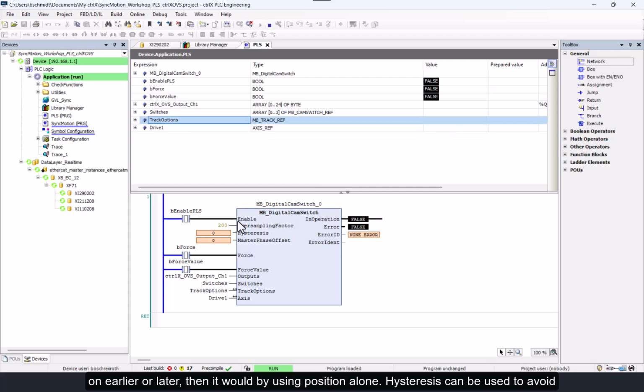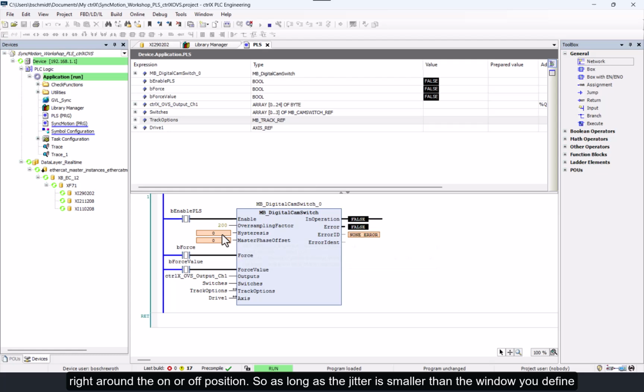Hysteresis can be used to avoid having the output toggle on and off if there's jitter in the position feedback right around the on or off position. So as long as the jitter is smaller than the window you define here, the output will not toggle on and off if it happens to be hovering right around the on position. The master phase offset can be used to shift all of the switches in one direction or another. So if I had a value of 10 in here, my on position of 90 degrees would now become 100 degrees, and my off position of 270 would now become 280. And this would apply to any other switches that I had configured.